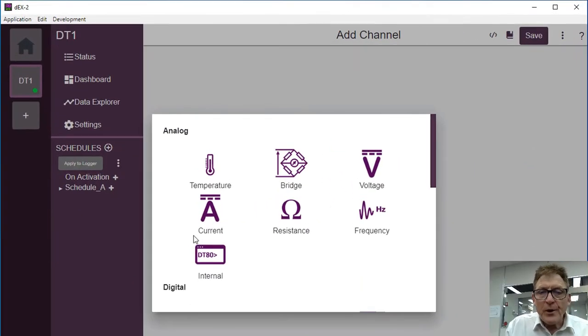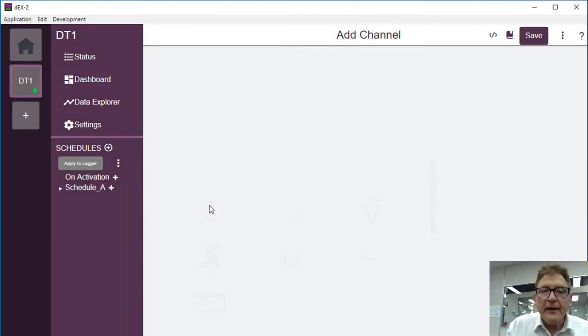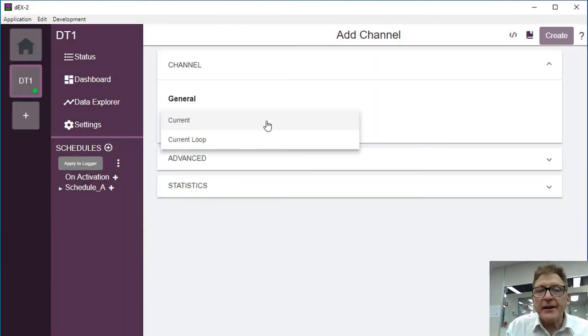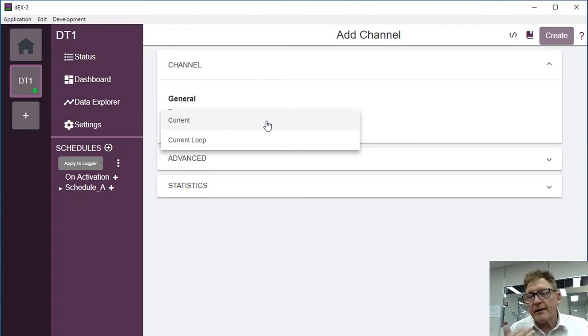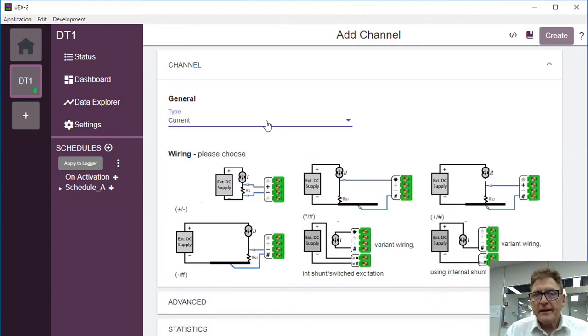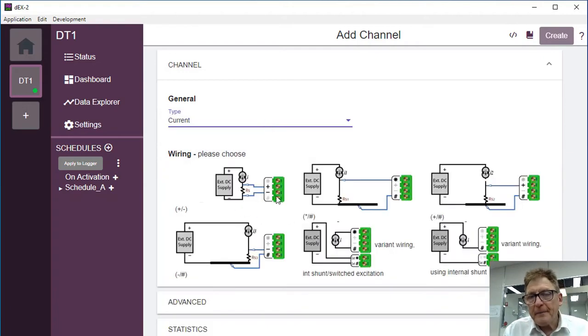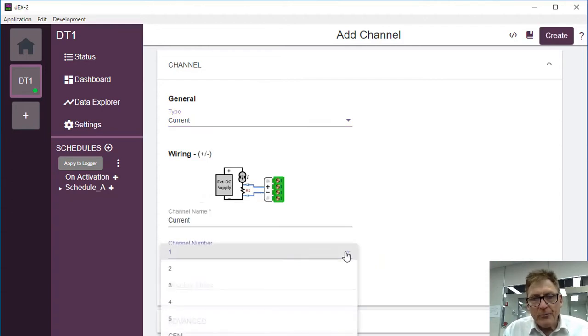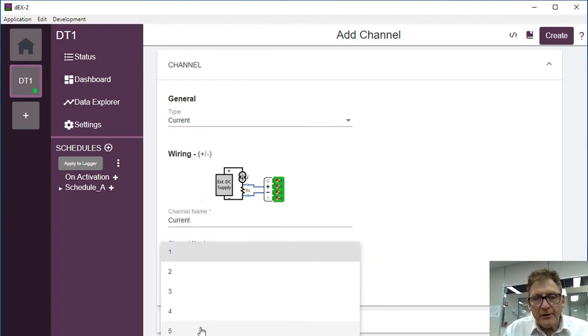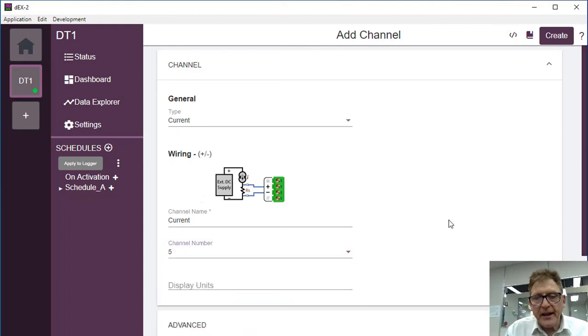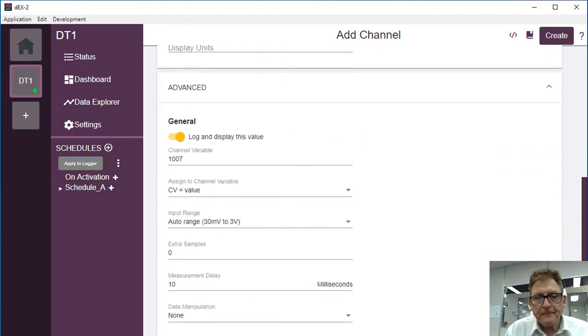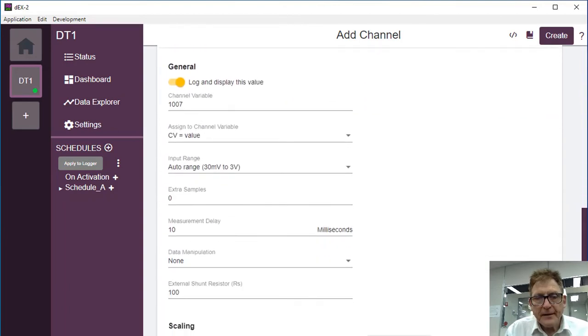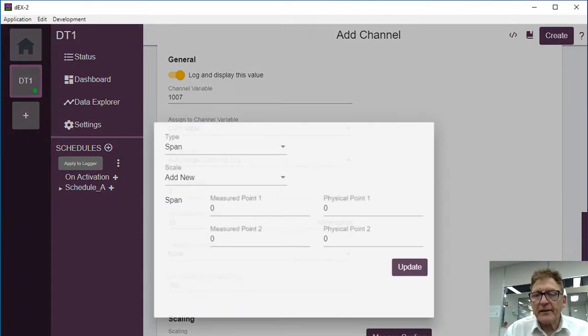So what I need to do, I need to add a current loop. In this case, again, I could use either loop, so it's zero to 100% or current. I'm going to use just for sake of argument current. We've wired it up again like this, and we've wired it to channel 5. We need to come down to advanced here, which I scroll down. Scaling. Manage scaling.